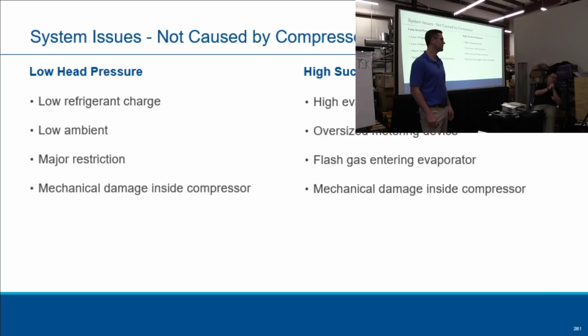We literally fire them up in there, and a lot of it has to do with the safety devices inside the scroll that people aren't aware of, that Trevor went over. Yeah. So just food for thought. You've got to be aware of that stuff, right? We test every compressor, so if you're getting a compressor that's not running, well, it does happen, right? The compressor maybe fell and got hit, banged up. Who knows how it shipped from our factory? But we know from our factory, and I've walked through it many times, that we test run every one. And there's a huge procedure to get them out.